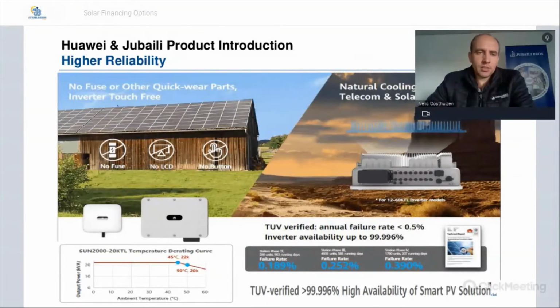There's no LCD screen. On the Huawei inverter, you've just got LED indicators. An LED indicator for your DC side, showing if everything is okay on your array. Then you've got the AC LED indicating if grid is available or not, or if the grid is unstable. You've got a communication LED indicating whether your communication to the Huawei monitoring platform is okay, or if you've got a problem with internet connectivity. And then lastly, you have an alarm LED, which indicates if it's a minor or a major fault. The whole system is designed to work from your phone, so you can control everything from your cell phone, or you can also log in via a laptop or a computer. Everything is online, available for your monitoring 24/7.